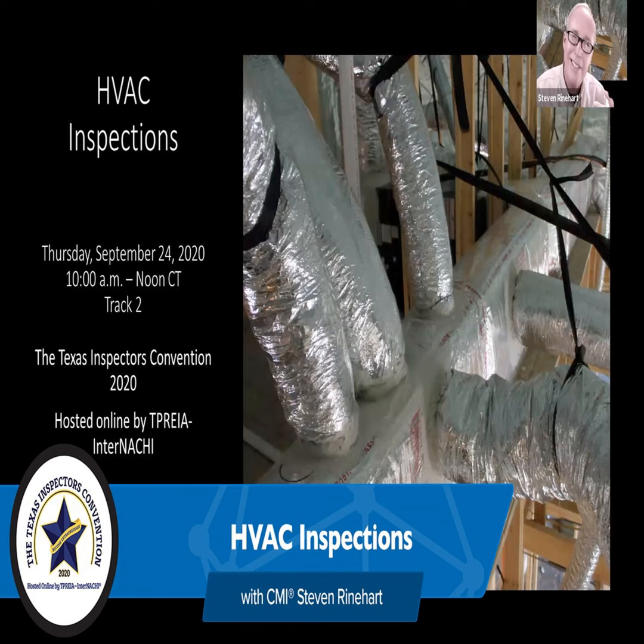And a lot of my registers, I go around and look at them. If I don't see 100 degrees coming out of a register and it's been running for a while, I start getting suspect. And I'll look at the closest one to the farthest one. But a lot of times I'll see 40, sometimes I'll see 50 degrees difference for a heat.